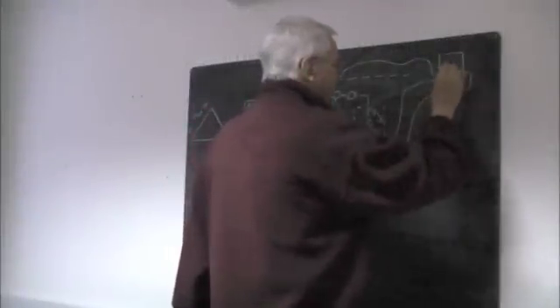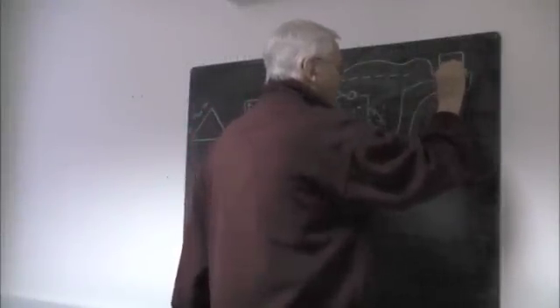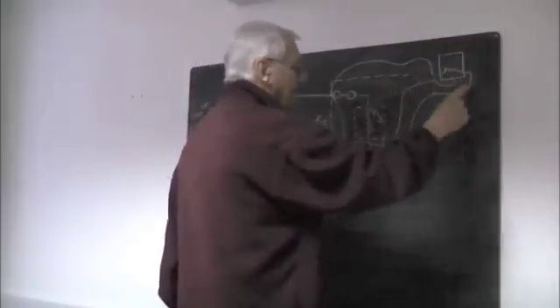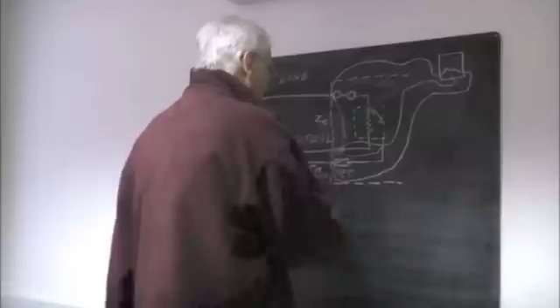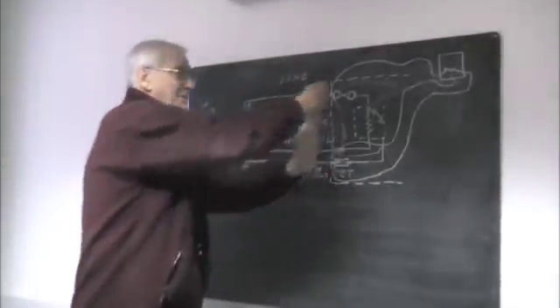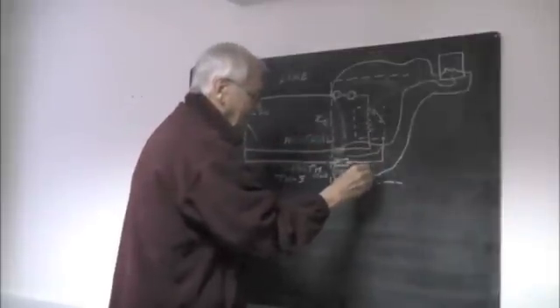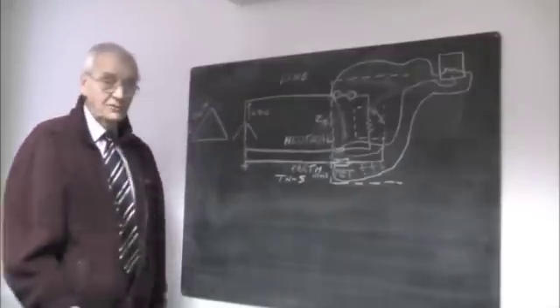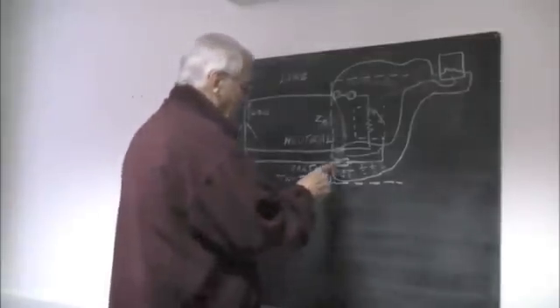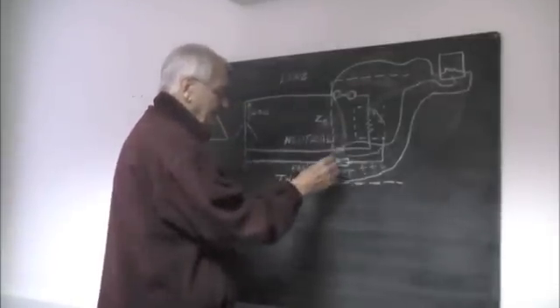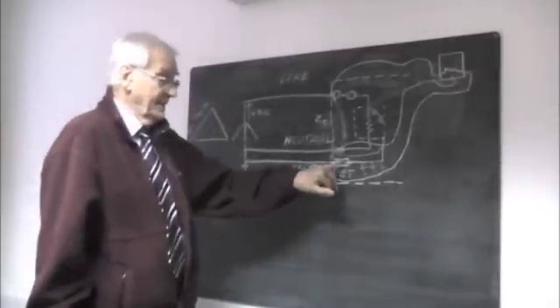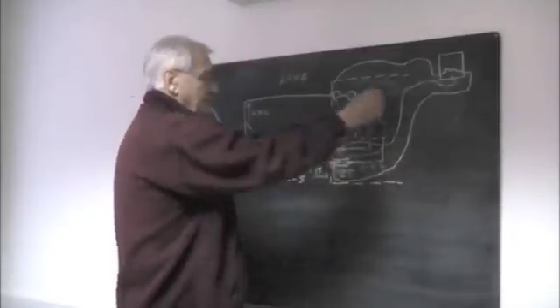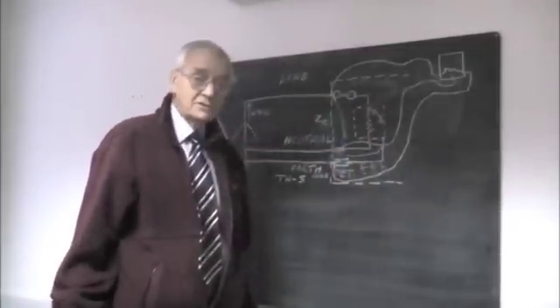Now when you press the button on this instrument, you're actually putting a low resistance across these two terminals from here to here and that's measuring the ZE. But to do that measurement and make sure you get an accurate reading, you don't want any of this part in it to give you any spurious earth connections for the current to go down. We want a true reading back to the star point of this transformer. So what we have to do is we've got to disconnect this earth here from that system and measure onto that earth. But naturally before we can take that earth connection off of there, we must disconnect the building supply, otherwise you'll have a whole electrical system operating in here without any earth protective device conductors on it at all.